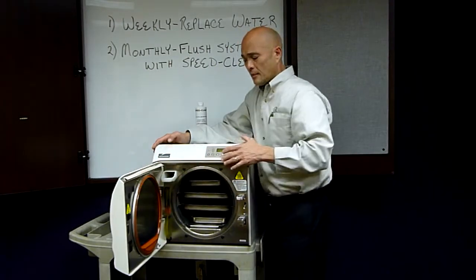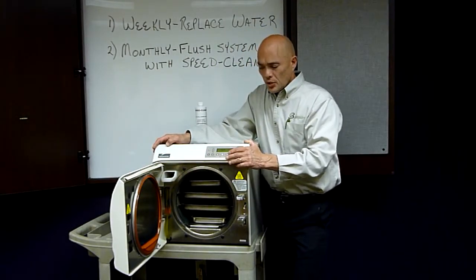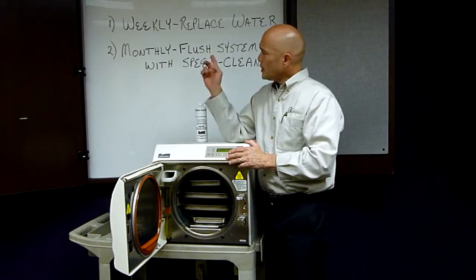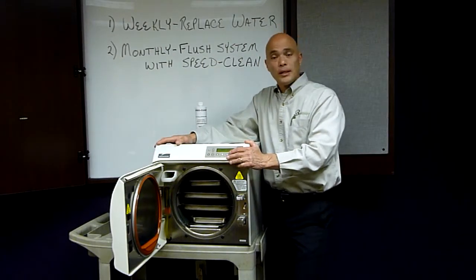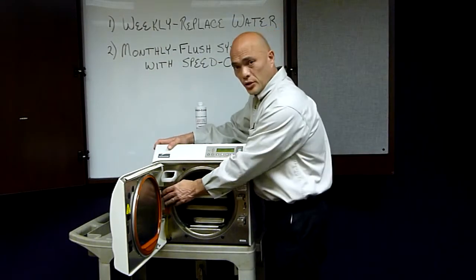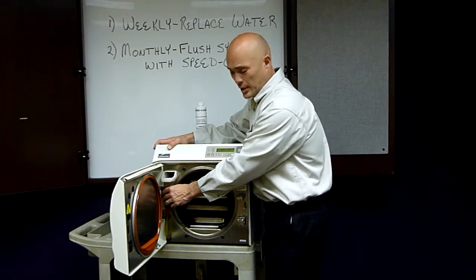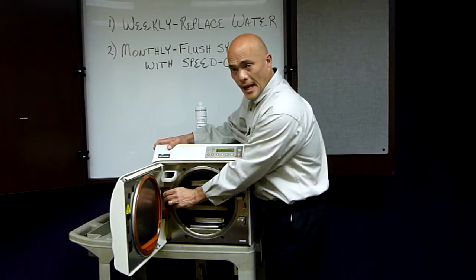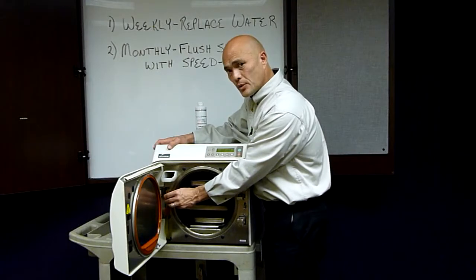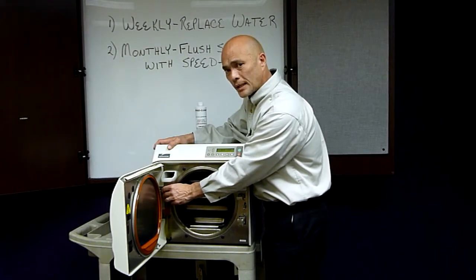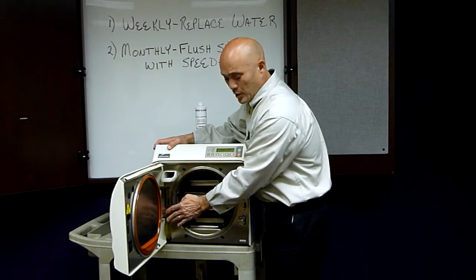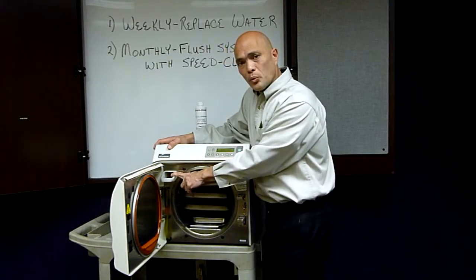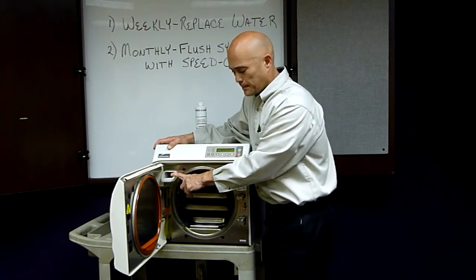Now let's go over the maintenance of your sterilizer. To start with, there's 2 things that you want to accomplish. Weekly, you want to make sure that you drain your water reservoir. You do that by pulling your tube loose, realizing that as soon as you drop this tube, water is going to come out. So have a bucket ready to go. Drain the reservoir completely, and then refill it with 1.4 gallons of distilled water.